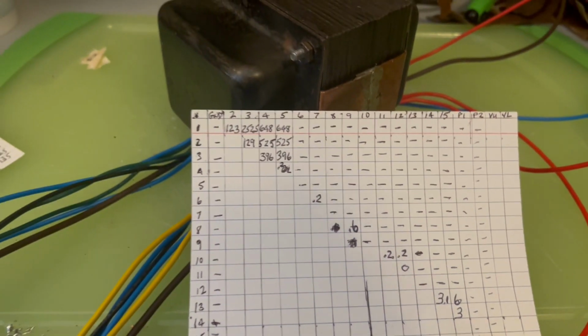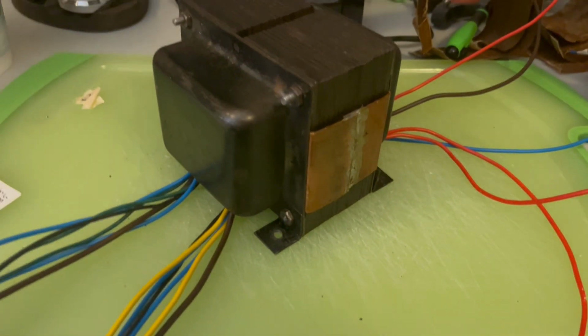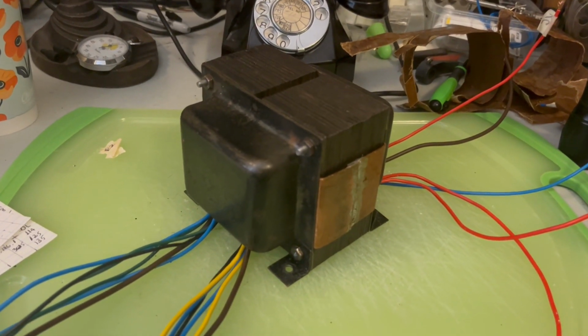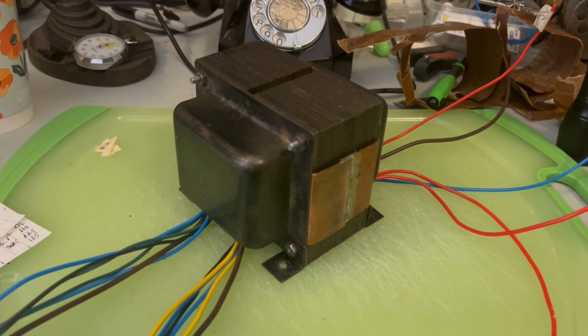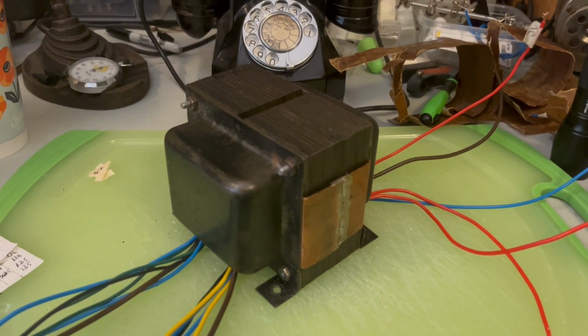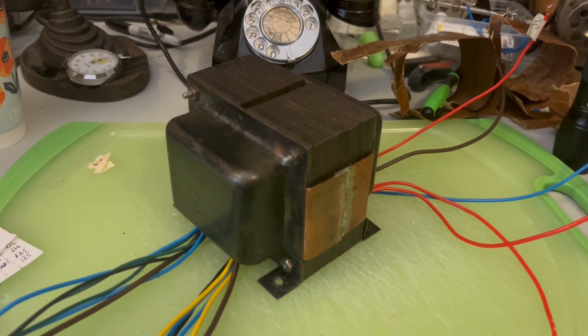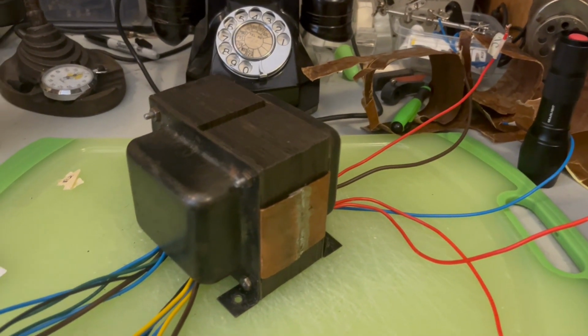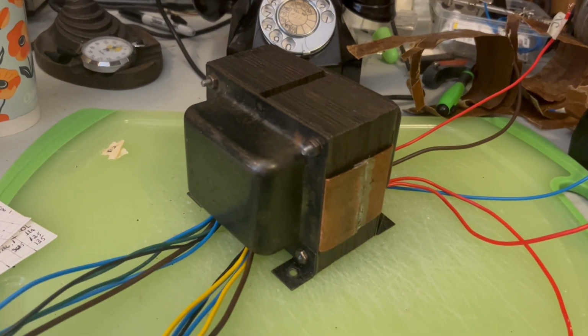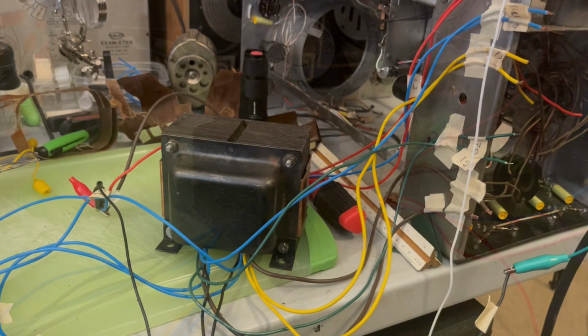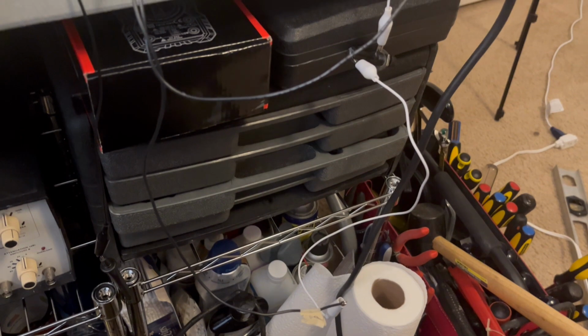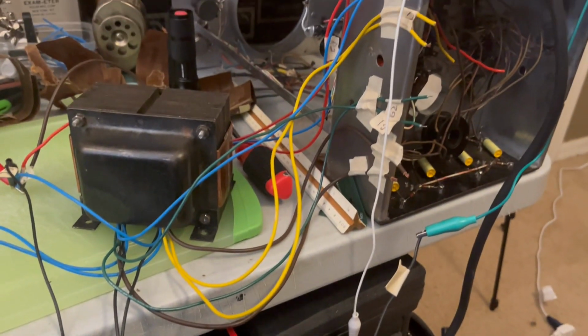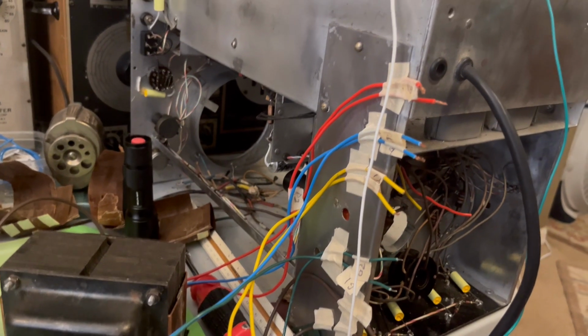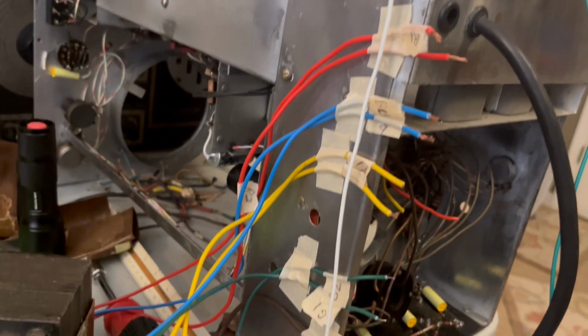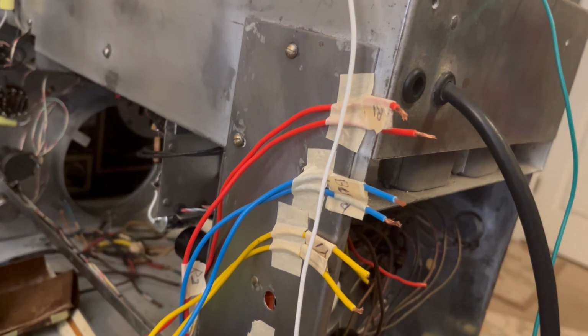We'll see what happens. The next thing that I need to do before I hook this thing up is to really do a no load test on it and check the voltages to see that we don't have any problems and that we're not blowing fuses anymore. So that's what's next. Okay, I've got the transformer wired through the fuse. It's down here somewhere. And I've got it wired through the switch. And each one of these is the secondaries tied together. There's a high voltage one.